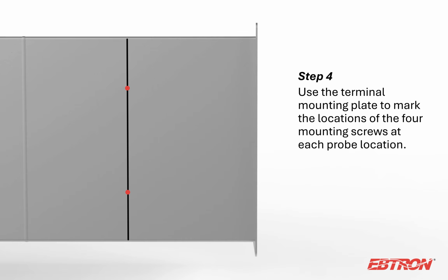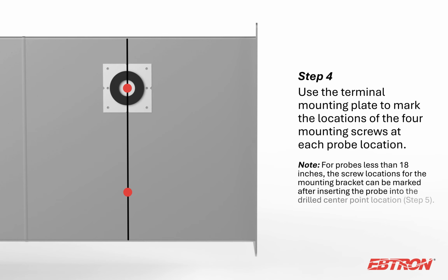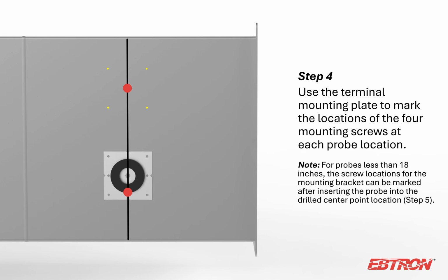Next, we'll use one of the terminal mounting plates that was previously removed as a template to mark the location of the 4 mounting screws. With the foam gasket pointing away from the duct or opening, position the center of the mounting plate with the center point marked in the previous step. Be sure that the center line notches on the mounting plate align with the line drawn on the outside of the duct or opening. Mark the location of the 4 mounting bracket screws. Repeat this step for each additional probe center point on both sides of the duct or opening.